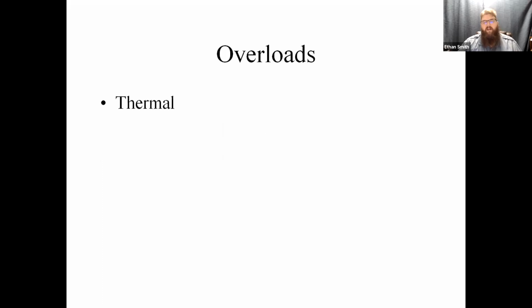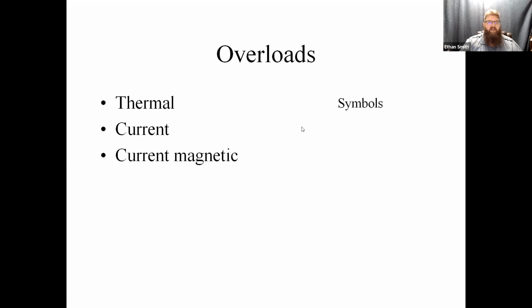Okay. Let's talk a little bit about overloads. So now we're into safety devices. We've got several different types of overloads. We've got thermal overloads. We've got current overloads, current magnetic overloads. Various different types. Let's talk about some symbols. A thermal overload is typically going to be depicted by having two contacts and usually a bent line in between them. This is indicating that this is a bimetal disc. When that thing heats up, it will curl up and actually break it. They're actually just pictorially describing what's going on inside that switch.